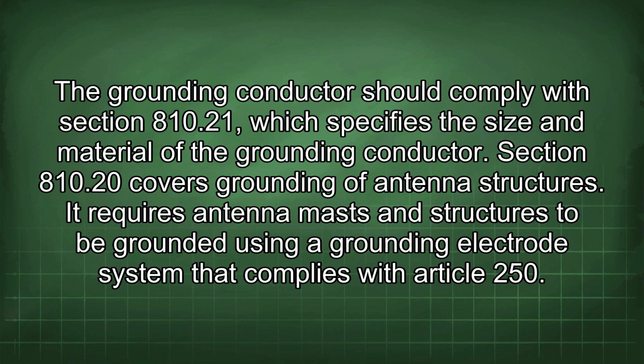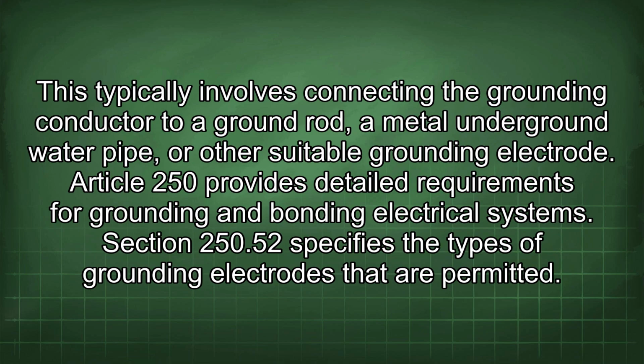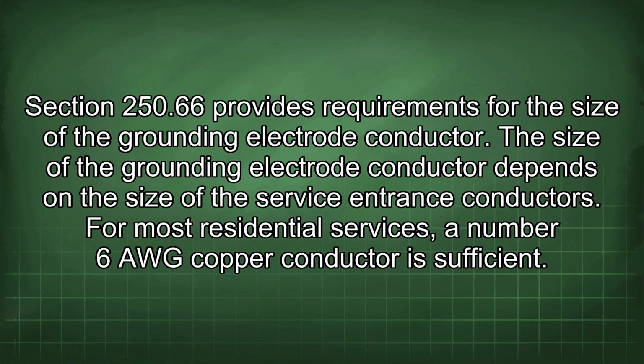It requires antenna masts and structures to be grounded using a grounding electrode system that complies with Article 250. This typically involves connecting the grounding conductor to a ground rod, a metal underground water pipe, or other suitable grounding electrode. Article 250 provides detailed requirements for grounding and bonding electrical systems. Section 250.52 specifies the types of grounding electrodes that are permitted. Section 250.66 provides requirements for the size of the grounding electrode conductor.